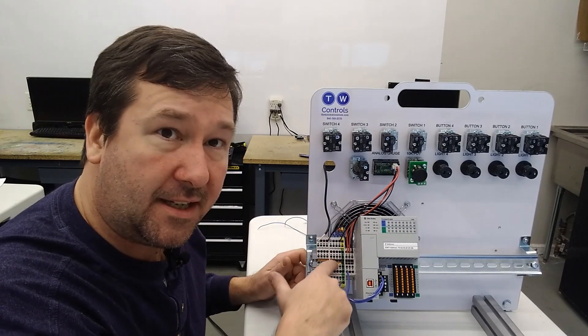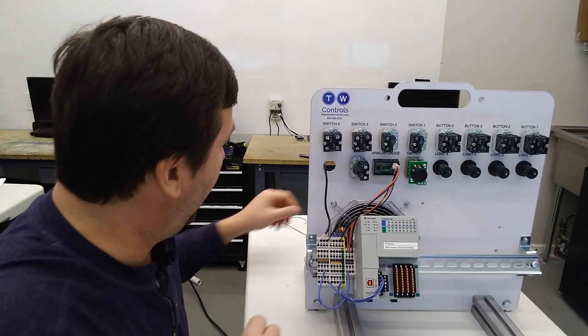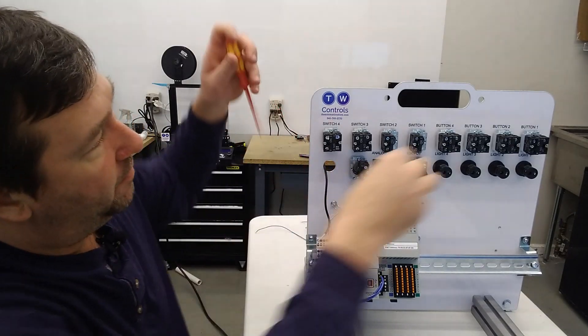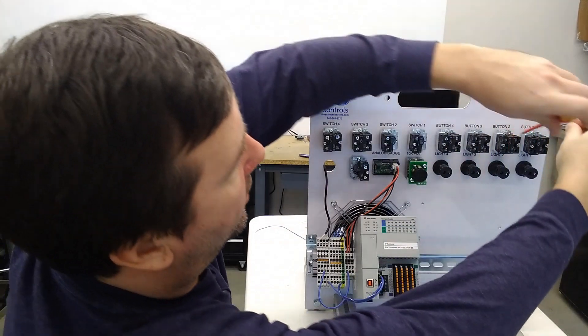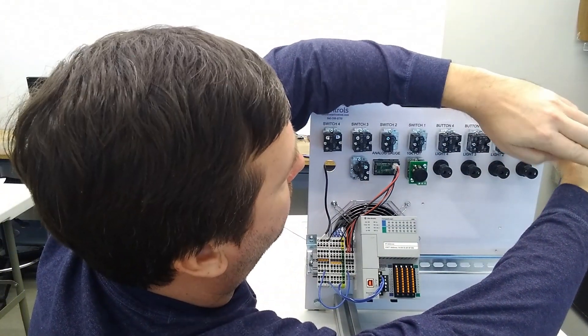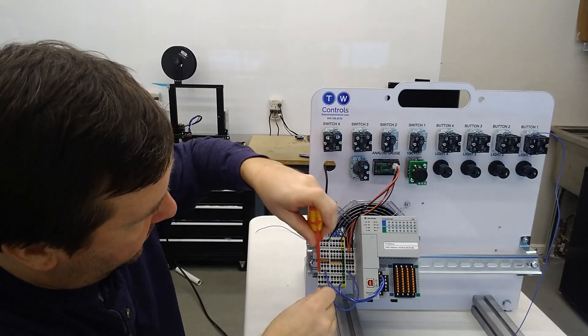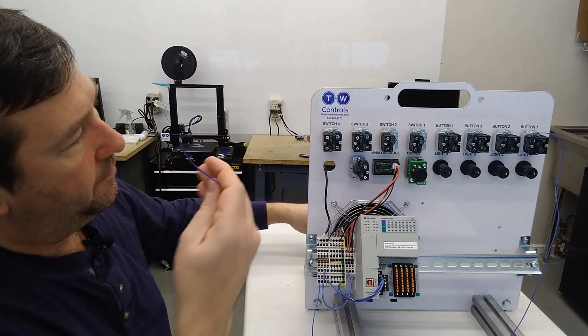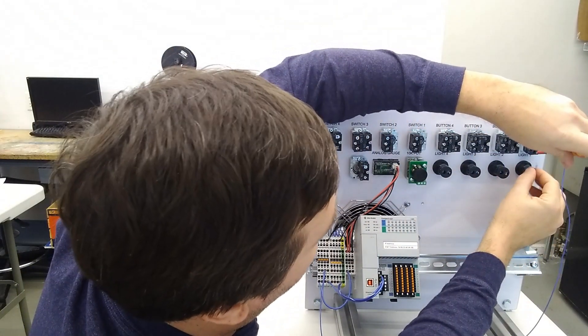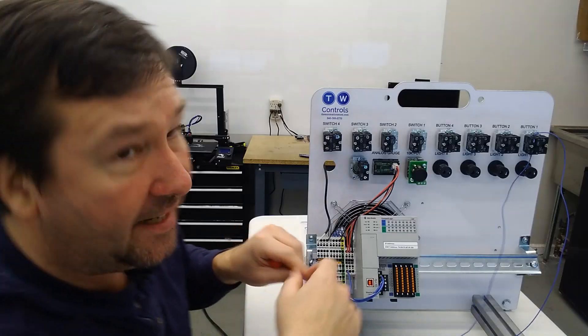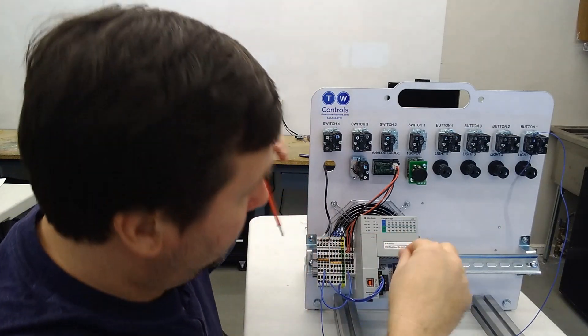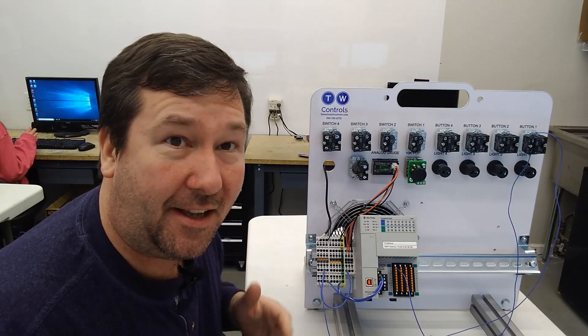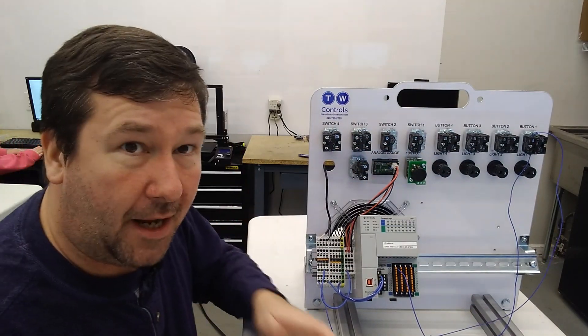It has a 24 volt DC power supply right here. And that 24 volt DC power supply has landed on these sets of terminals. So the left set of four terminal blocks here is our plus 24 volt. And the right set of four terminal blocks is the zero volt or the minus. We're going to start by connecting a wire to the top of our green contact. And we'll connect it to plus 24 volt. And then we're going to connect a wire from the bottom of our green contact. And we're going to connect it to input zero.